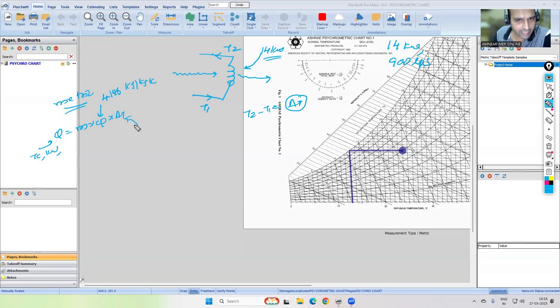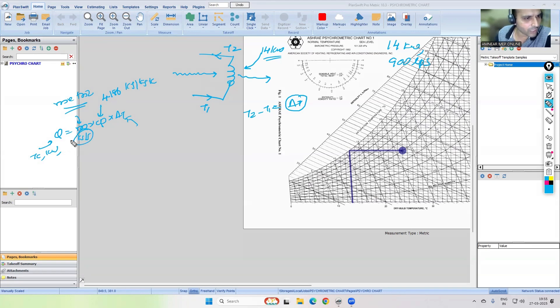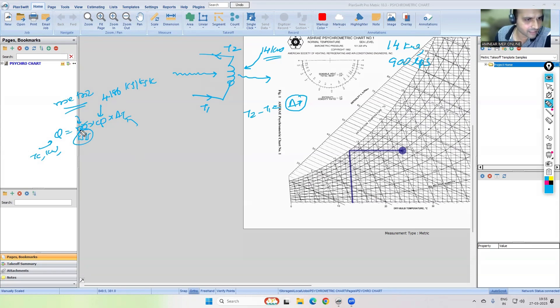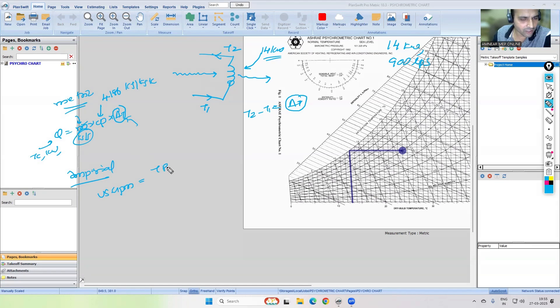How much delta T should we consider? In metric standard, delta T is typically 5.5 degrees Celsius. In imperial standard, we use 10 degrees Fahrenheit, which is equivalent. For converting a differential temperature: delta T in °F divided by 1.8 gives delta T in °C, or delta T in °C multiplied by 1.8 gives delta T in °F. That you have to remember.